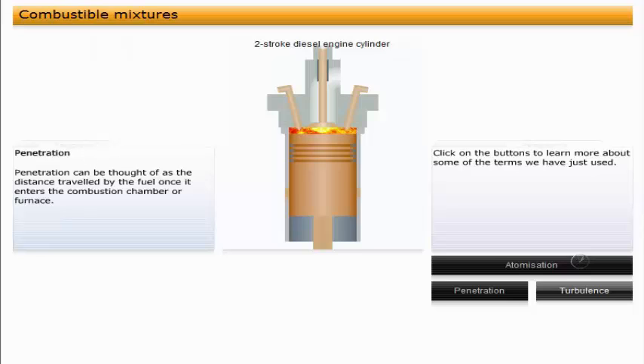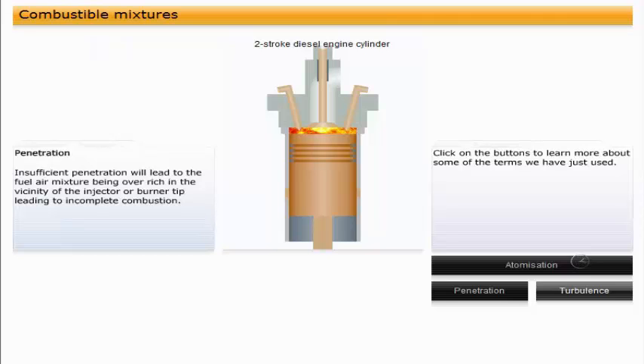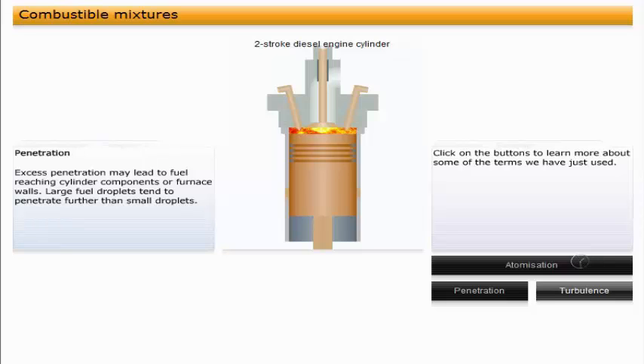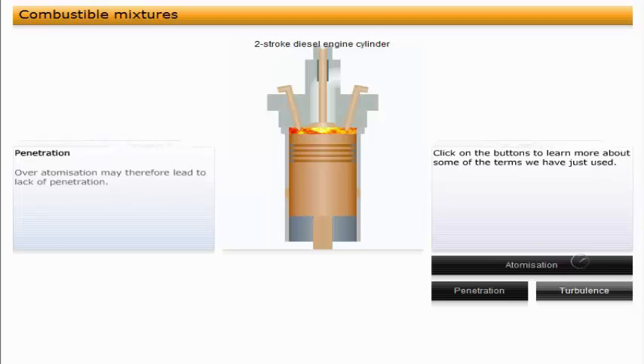Penetration can be thought of as the distance traveled by the fuel once it enters the combustion chamber or furnace. Insufficient penetration will lead to the fuel-air mixture being over-rich in the vicinity of the injector or burner tip, leading to incomplete combustion. Excess penetration may lead to fuel reaching cylinder components or furnace walls. Large fuel droplets tend to penetrate further than small droplets. Over-atomization may therefore lead to lack of penetration.